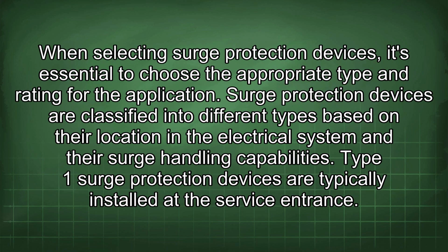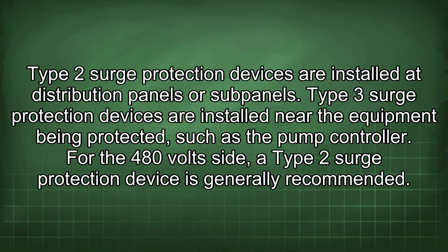When selecting surge protection devices, it's essential to choose the appropriate type and rating for the application. Surge protection devices are classified into different types based on their location in the electrical system and their surge handling capabilities. Type 1 surge protection devices are typically installed at the service entrance. Type 2 surge protection devices are installed at distribution panels or subpanels.